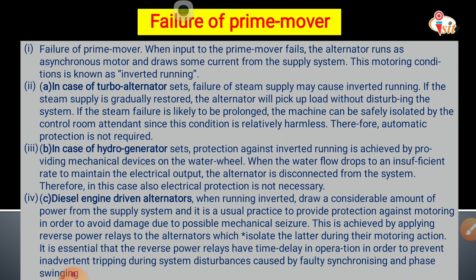The alternator will take current from the supply system, and this condition is known as inverted running. In the case of a turbo alternator, failure of steam supply may cause inverted running. If the steam supply is gradually restored, the alternator will pick up load without disturbing the system. If the steam failure is likely to be prolonged, the machine can be safely isolated by the control room attendant since this condition is relatively harmless. Therefore, automatic protection is not required for a turbo alternator.